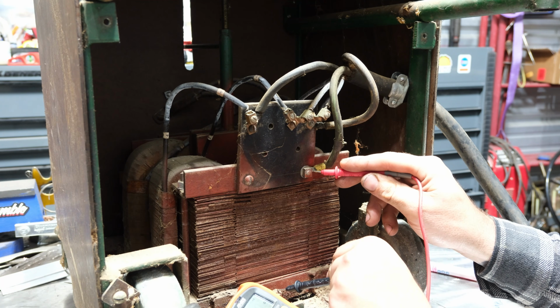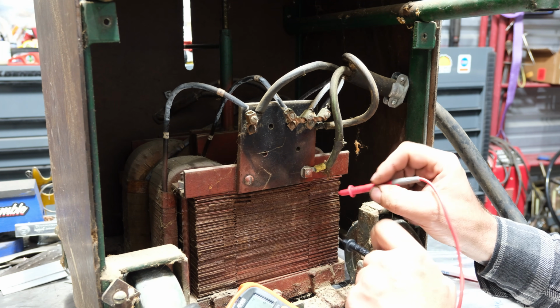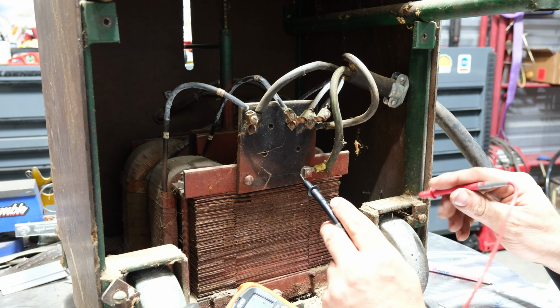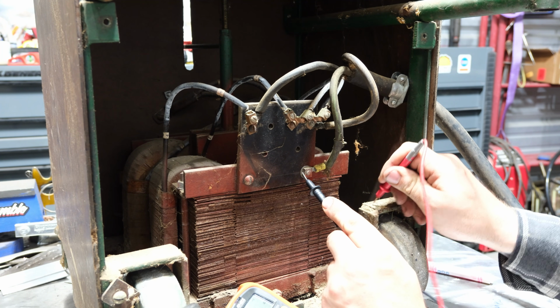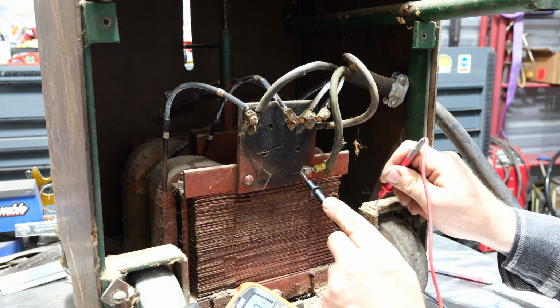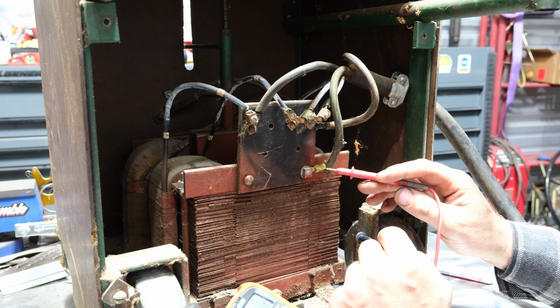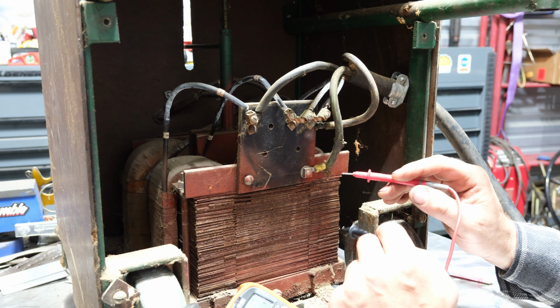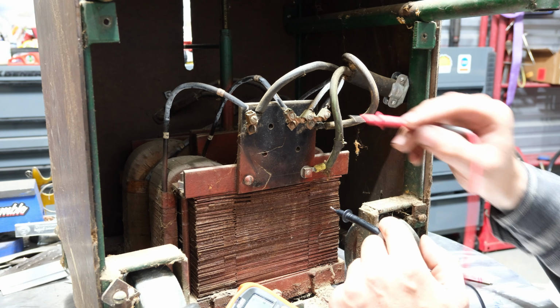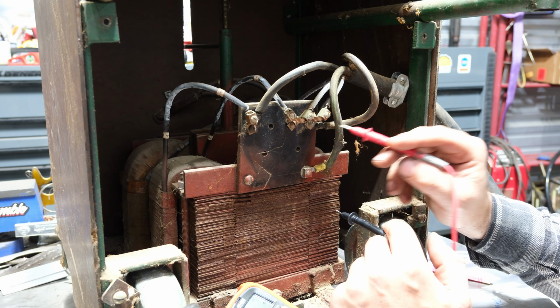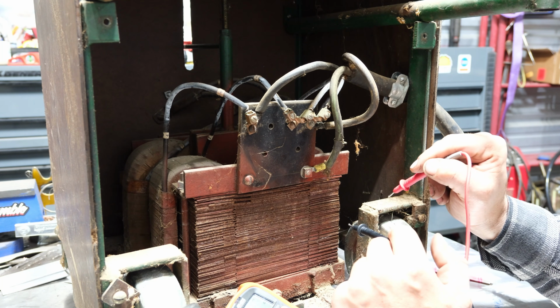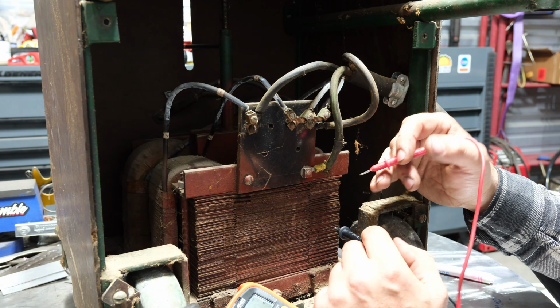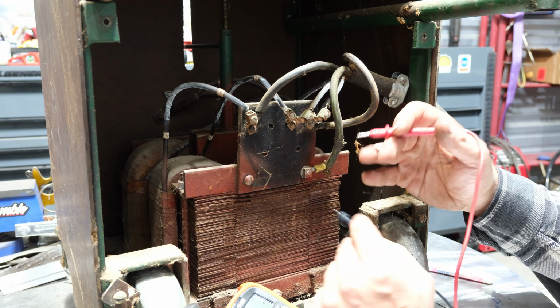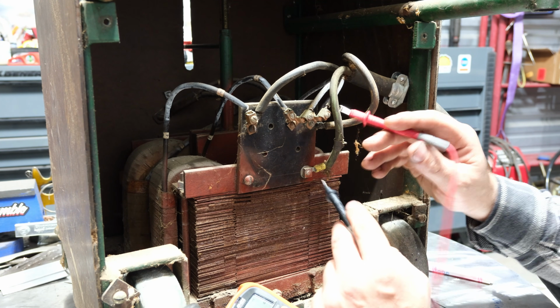First thing I'm going to do is touch, and you can see this being grounded to the core of the transformer. It has continuity there. It probably has continuity over here. Paint's a little rough, and that would make sense. Most welders, the case is grounded to the ground plug, so that's all normal. That's done that way so that if your wire, for whatever reason, shorts out, that it will trip the breaker because it gives it a path back through the ground wire to cause a short, more or less a high amperage drain on the breaker, so it trips.